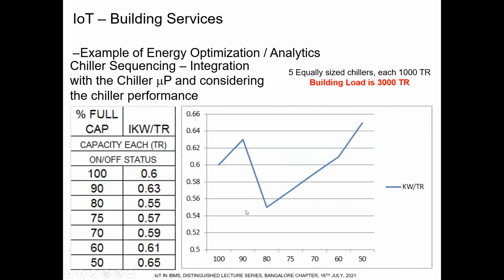The kilowatt per ton goes to a very low value compared to the other percentages. Okay, this is 100% load. You can see here in this chiller, in this particular example, at 80%, the chiller is consuming 0.55 kilowatt per ton. And at 75% it consumes 0.57 kilowatt per ton. This is the cataloged value of the chiller manufacturer.